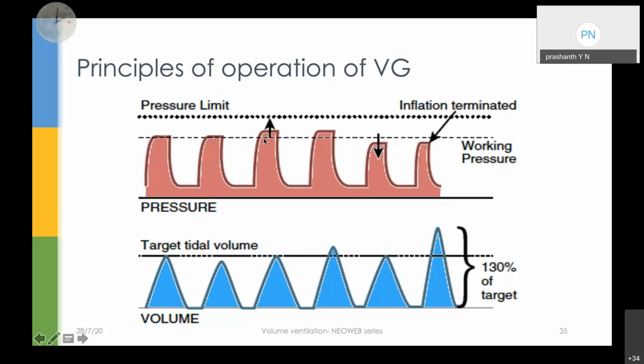Mind you, the Dräger also has a safety feature: if by any chance the volume increases to more than 130% of the target, for whatever reason, it cuts off the pressure. Probably it cuts off the I time also. Other than that, it doesn't touch the I times. It just takes feedback from the previous exhaled tidal volumes to set the PIP for the next breath. So this is how it is.